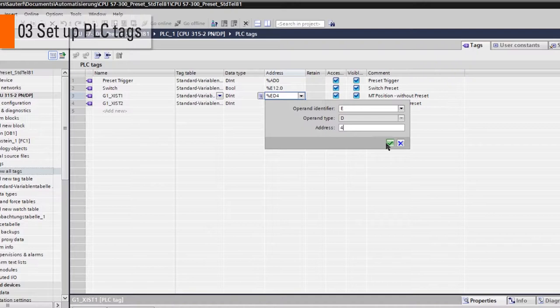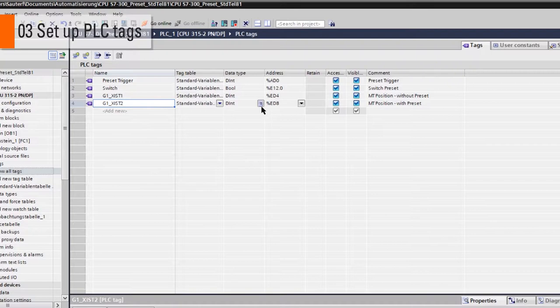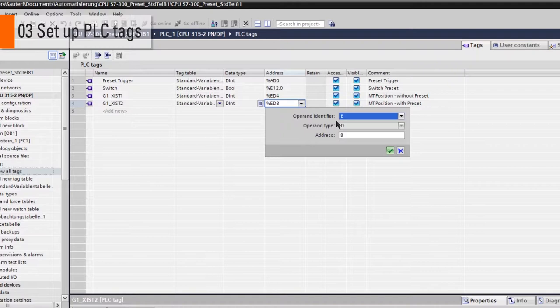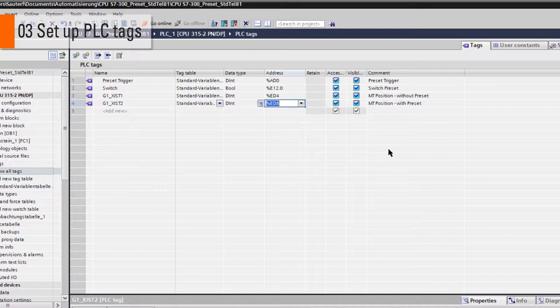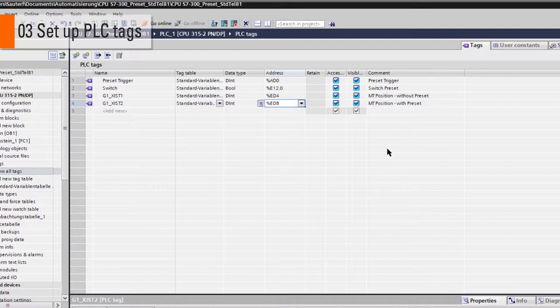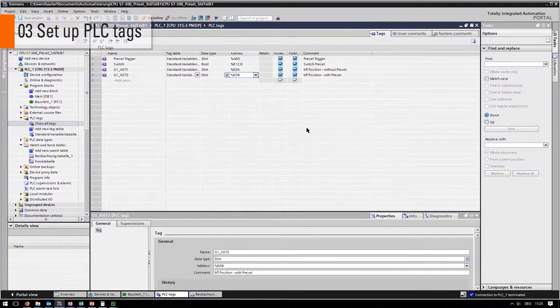Fourth, G1XIST2, which is a double integer value that starts on input address 8. The difference between XIST1 and XIST2 is that XIST1 does not consider the preset operation but instead a cache value. XIST2 displays the actual encoder position and takes the last preset into consideration.